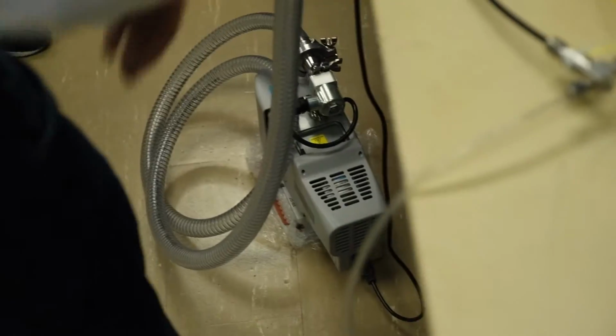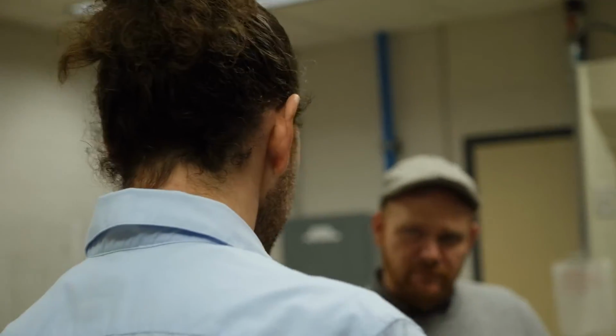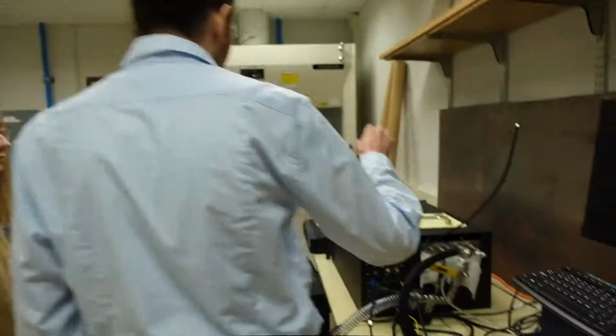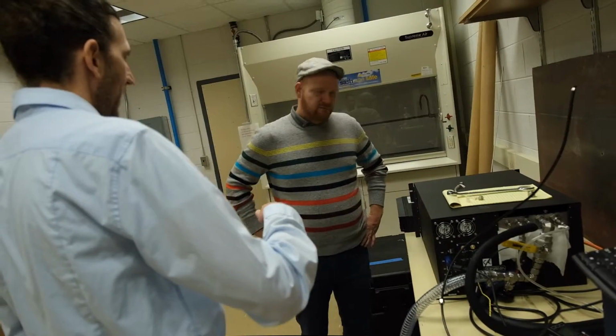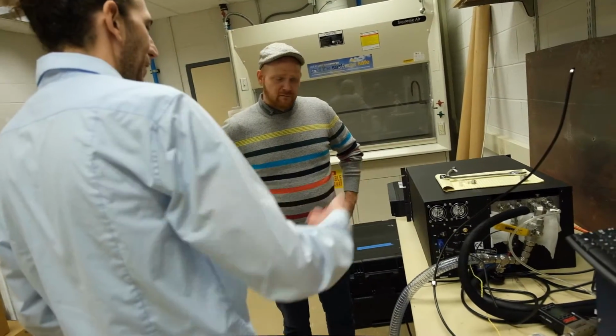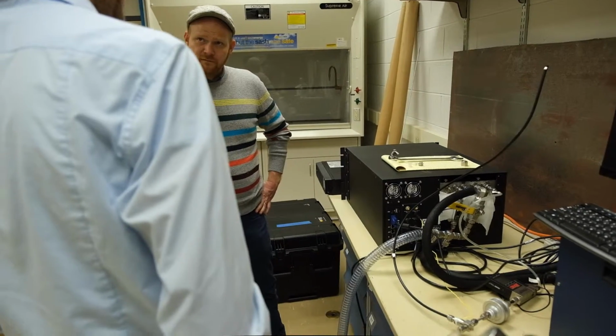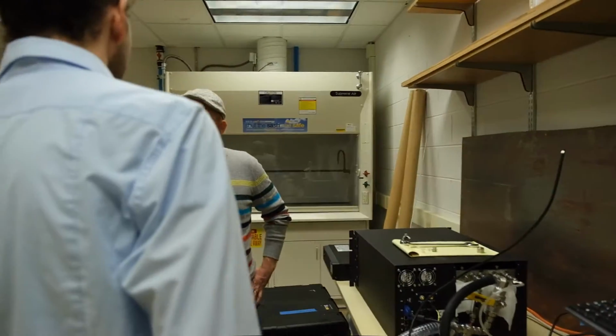And then what is this? The pump just pumps the air out? It's a vacuum pump, so it draws air. When we fly, the air flow rate is about 1.5 liters per minute, so it's a pretty good flow of air. The instrument measures at a reduced pressure compared to the atmosphere. It's at roughly 40 torr, while atmosphere is like 760, so about 5% of atmospheric pressure. It's basically under vacuum, but that's to make the optimal measurement.